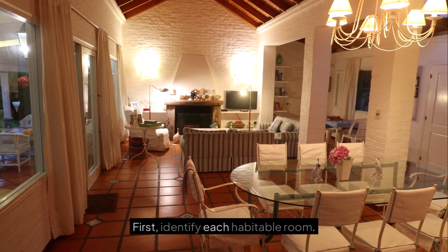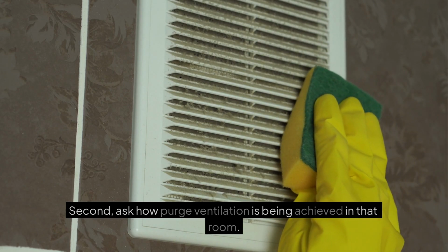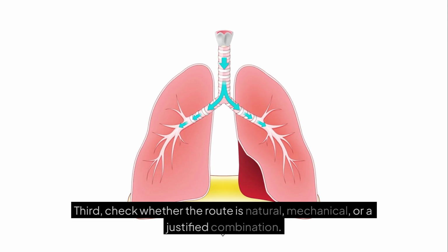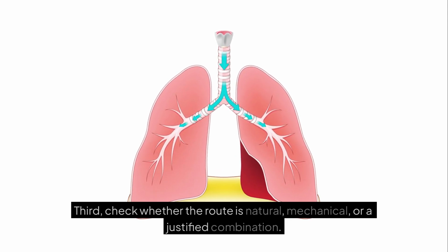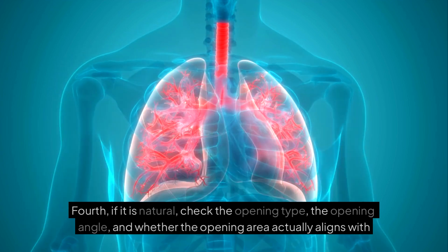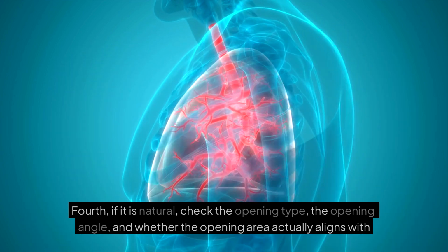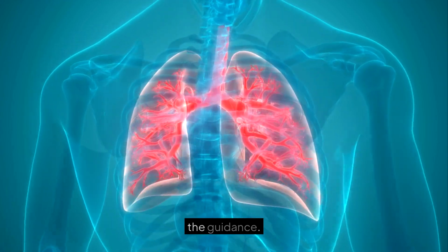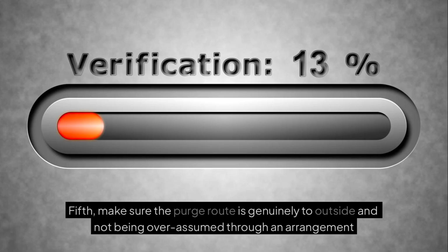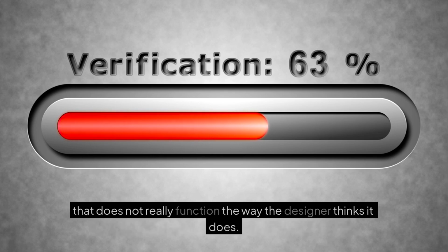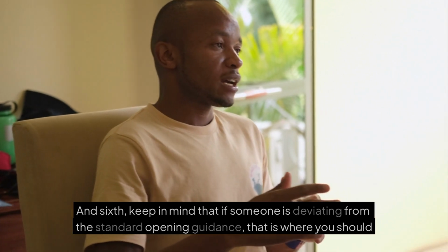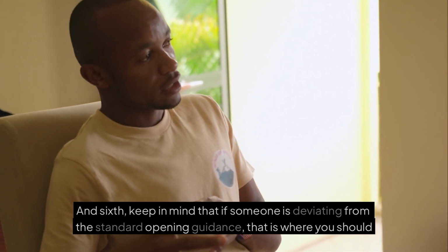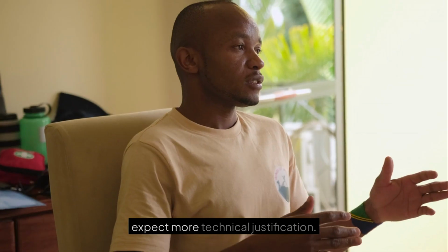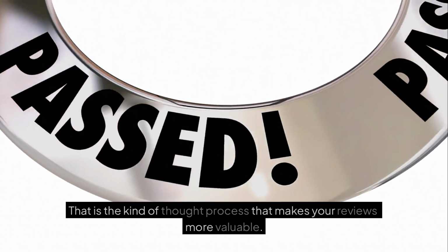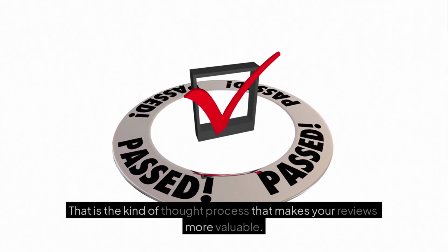First, identify each habitable room. Second, ask how purge ventilation is being achieved in that room. Third, check whether the route is natural, mechanical, or a justified combination. Fourth, if it is natural, check the opening type, the opening angle, and whether the opening area actually aligns with the guidance. Fifth, make sure the purge route is genuinely to outside and not being overassumed through an arrangement that does not really function the way the designer thinks it does. And sixth, keep in mind that if someone is deviating from the standard opening guidance, that is where you should expect more technical justification. That is the kind of thought process that makes your reviews more valuable.